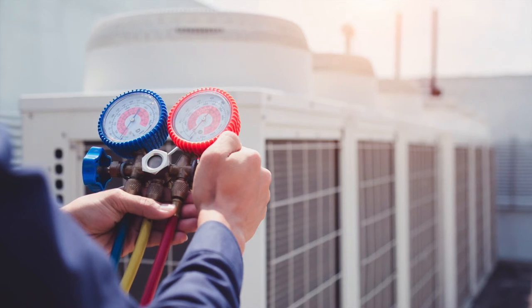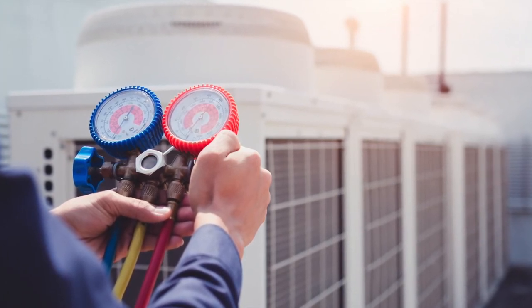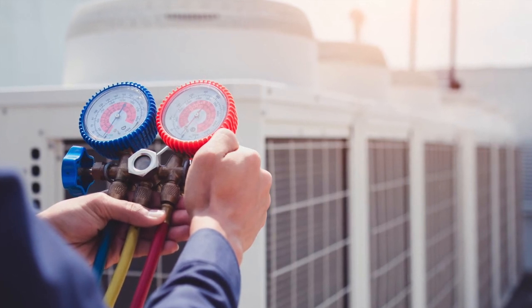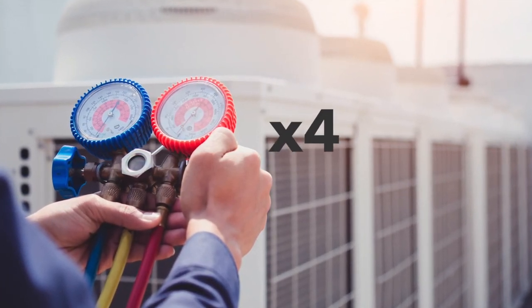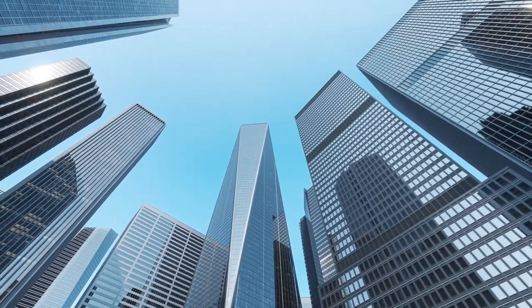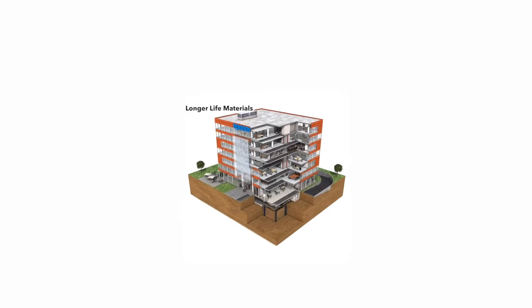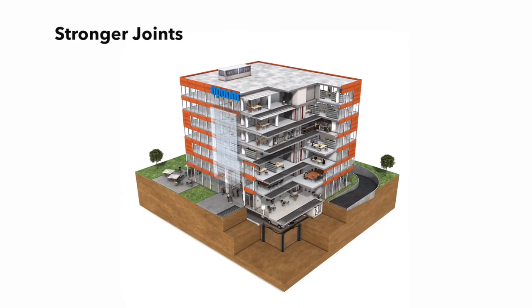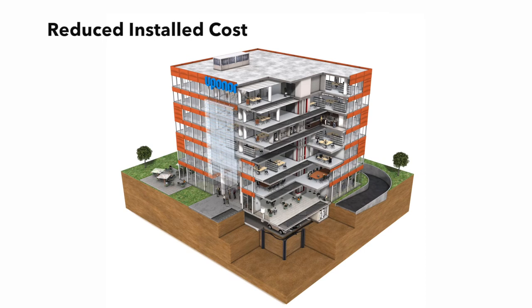The hydronic advantage can be summarized as, whatever the refrigerant in that building, it will have a GWP times 1. That is, the unit refrigerant volume times 1. If you add refrigerant volume in the building in the form of field refrigerant tubing to multiple spaces, you now have a GWP times 2, 3, 4, or more. There is no good reason to distribute comfort in a building with refrigerant when water will use 1/10 the horsepower and can be easier to install. Today's hydronic systems use longer life materials, stronger joints, and reduced installed cost due to speed and flexibility, a topic we will discuss in more detail.